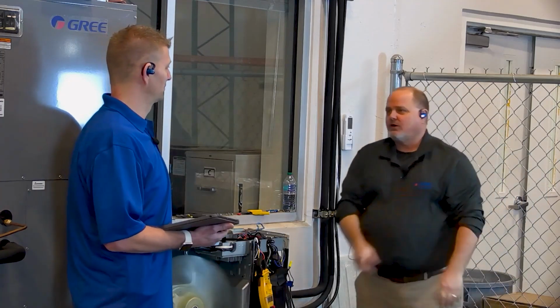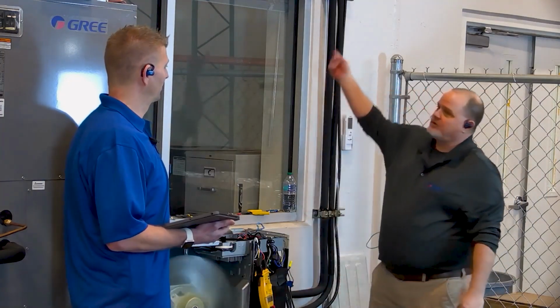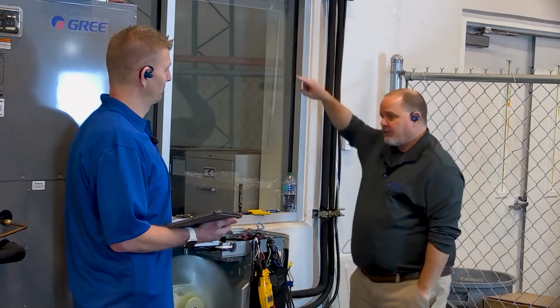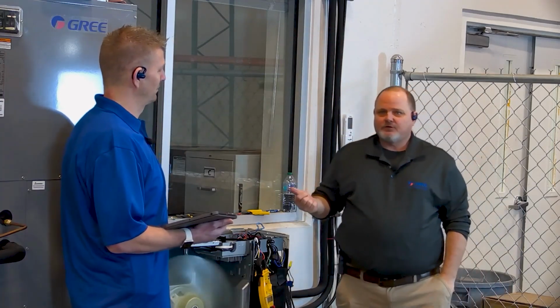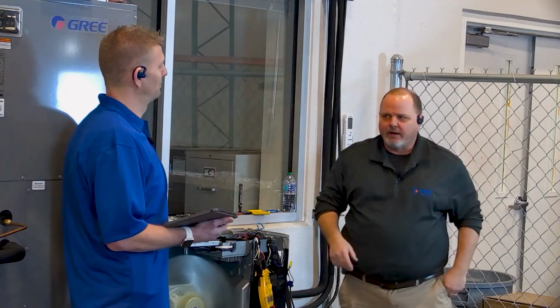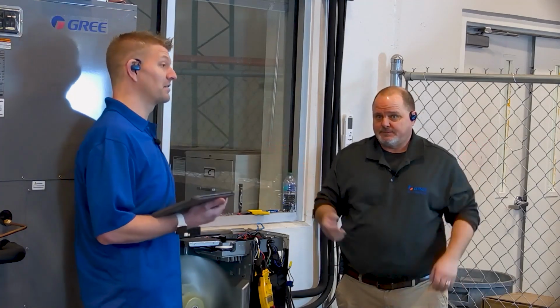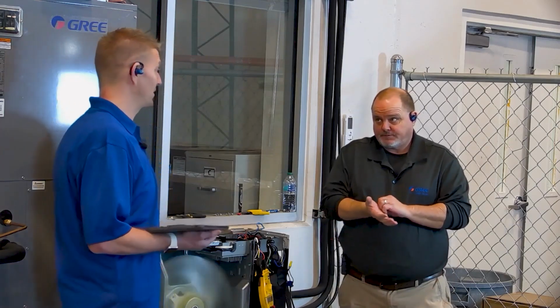Because if you follow that single zone piping diagram, your metering device is in the outdoor unit. If we're not feeding that refrigerant through, and we're not getting that refrigerant back, the compressor's going, hey, what's going on here? It thinks it's out of gas. Right. And the other thing is, the FO code is a hard reset code. So you've got to do a 10-minute hard reset, power it back on, and if it goes into FO right away, then I'd be looking at sensors. If it starts up, then we'd be looking at restriction.